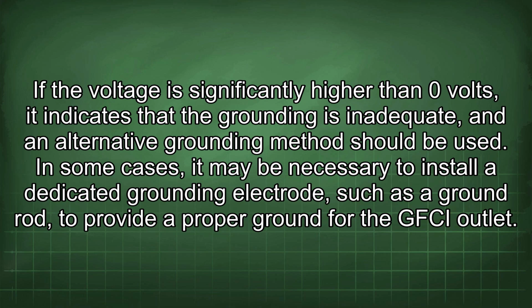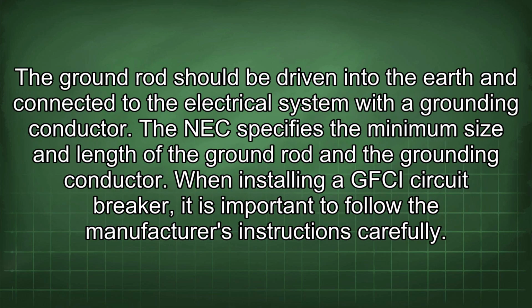If the voltage is significantly higher than 0 volts, it indicates that the grounding is inadequate and an alternative grounding method should be used. In some cases, it may be necessary to install a dedicated grounding electrode, such as a ground rod, to provide a proper ground for the GFCI outlet. The ground rod should be driven into the earth and connected to the electrical system with a grounding conductor. The NEC specifies the minimum size and length of the ground rod and the grounding conductor.